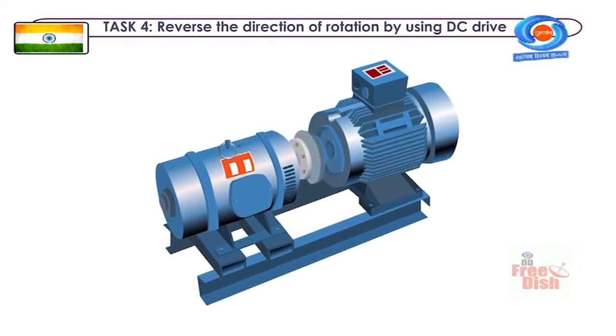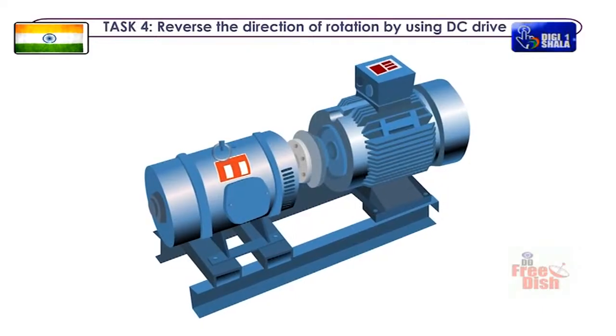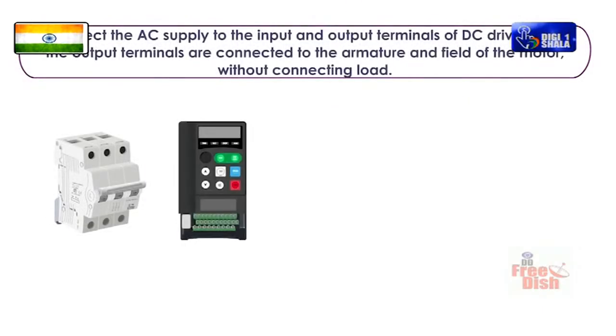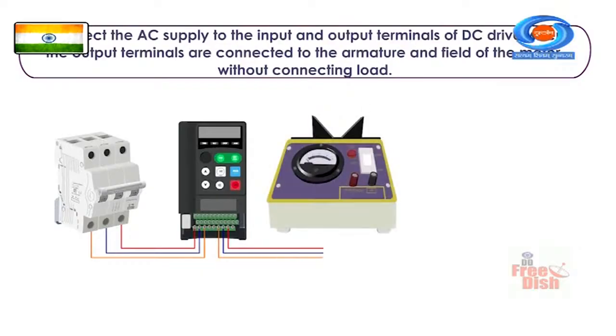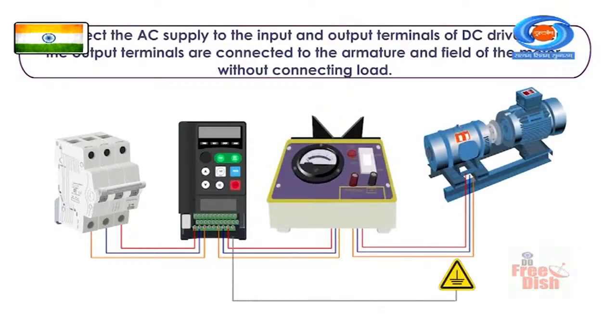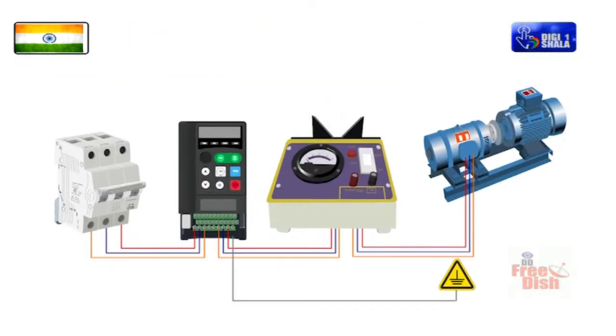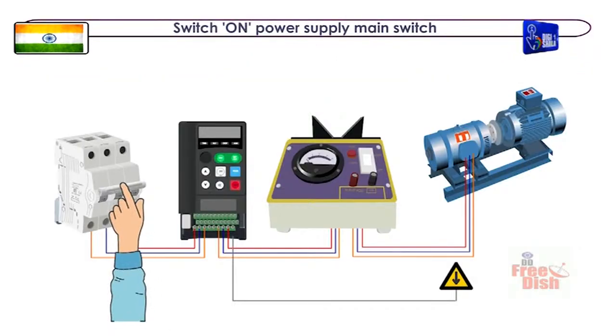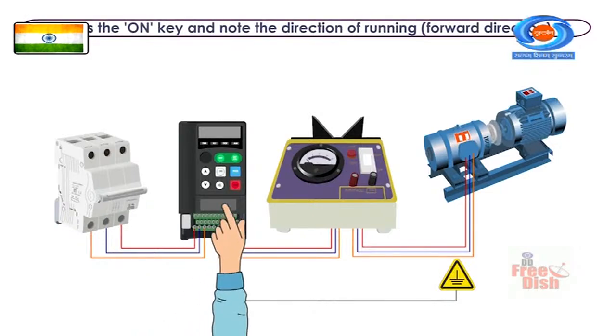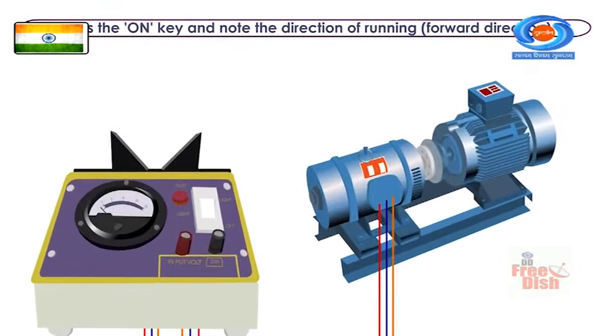Task 4. Reverse the direction of rotation by using the DC drive. Connect the AC supply to the input terminals of the DC drive, with the output terminals connected to the armature and field of the motor, without connecting load. Switch on the power supply main switch. Press the on key and note the direction of running.